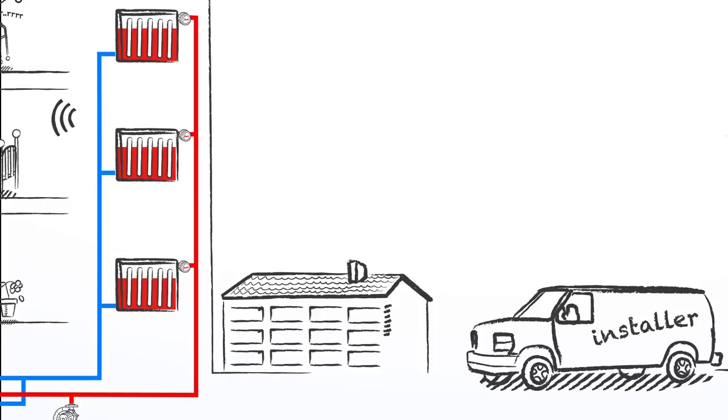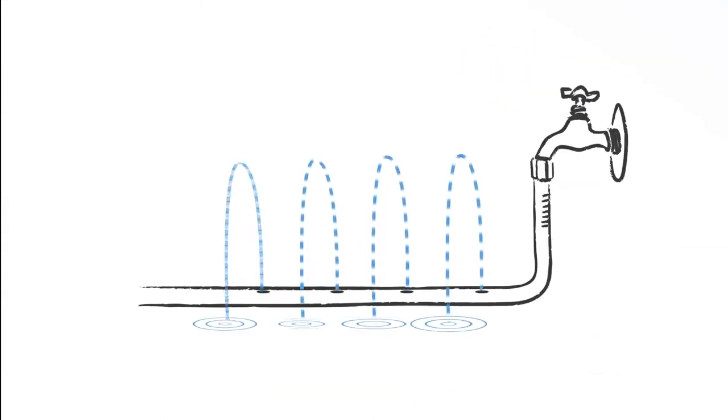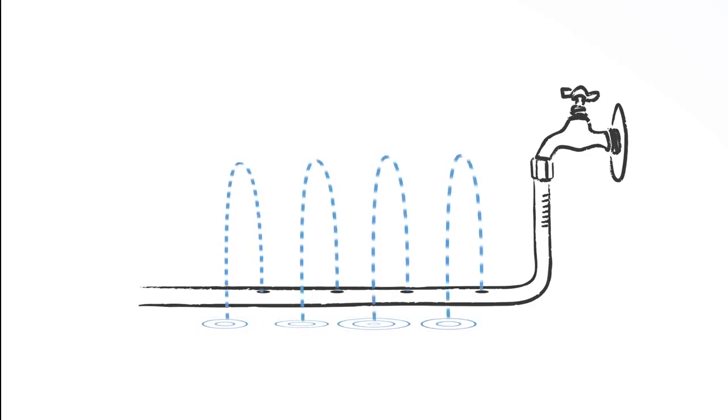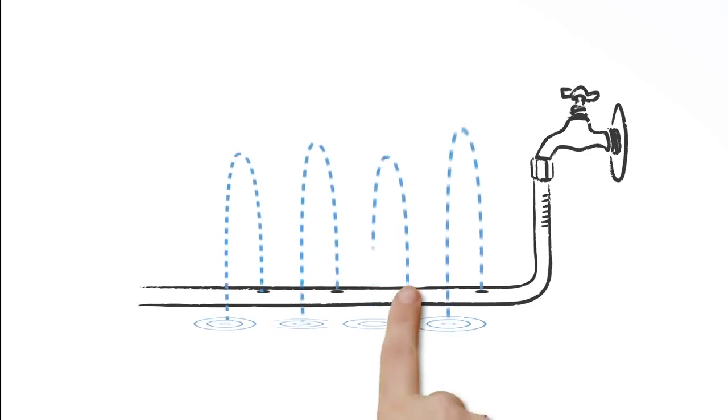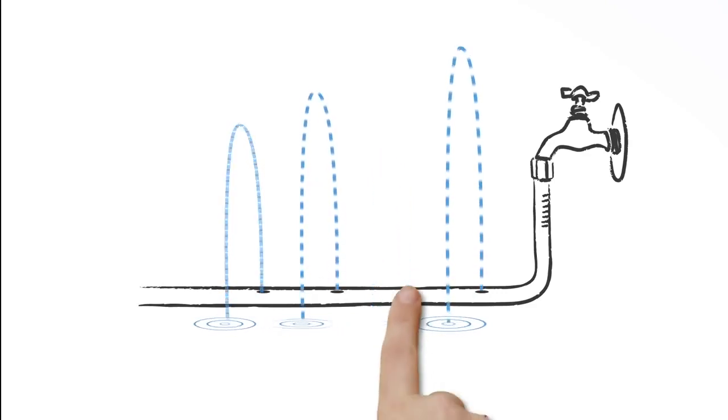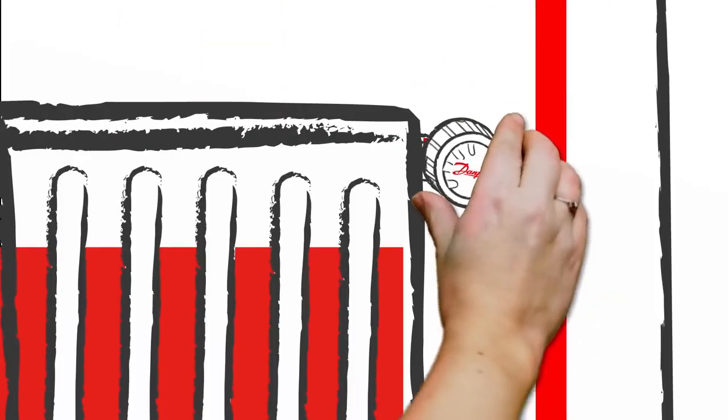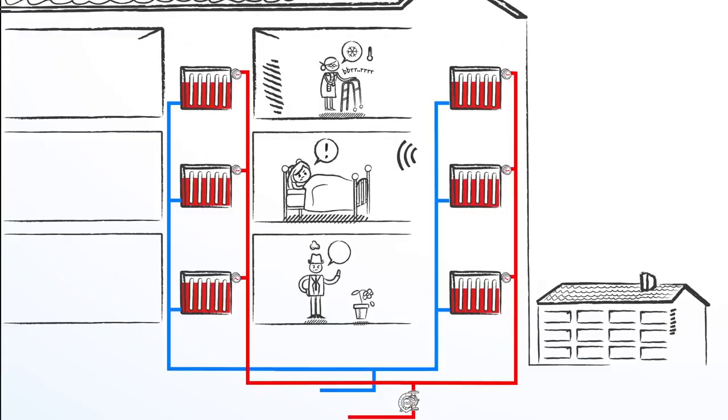So now we have balance in each radiator. But what happens if heating load changes because of weather conditions or when people open or close the radiators? The water redistributes and more water will flow to the other radiators.